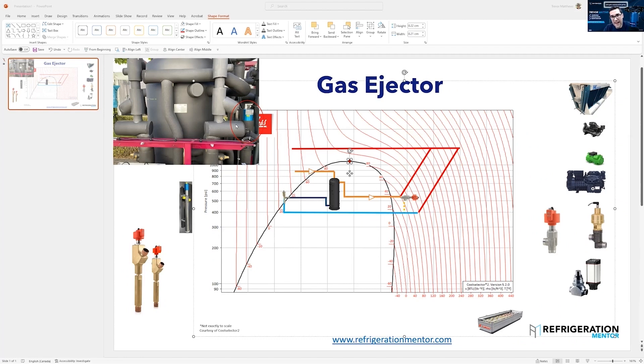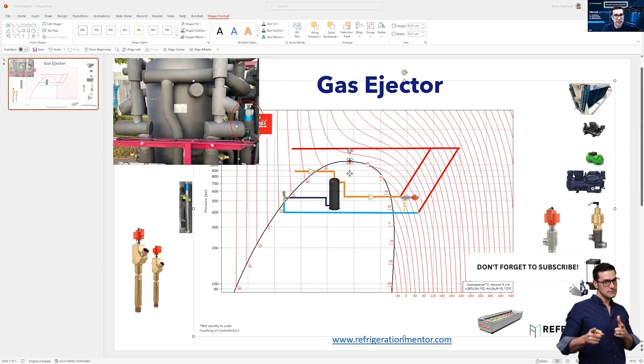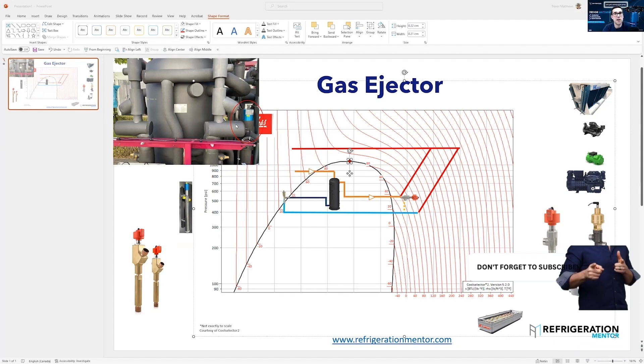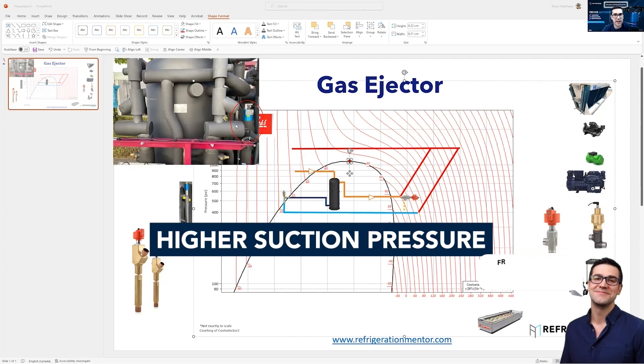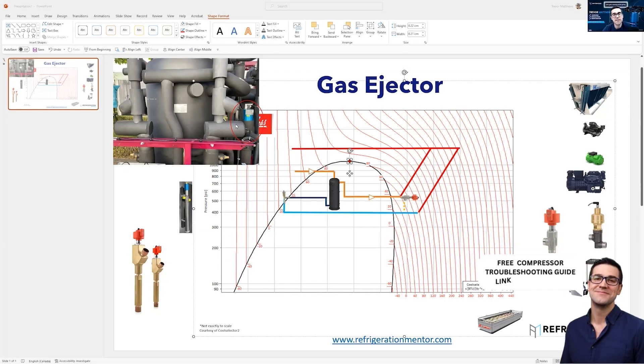The whole purpose of the gas ejector, in the simplest terms, is so the medium temp transcritical compressors don't have to do the work or as much work. It's taking the load from the medium temp transcritical compressors and putting it on parallel compression. The difference is parallel compression runs at a higher suction pressure, more like the flash tank pressure, versus the medium temp suction.